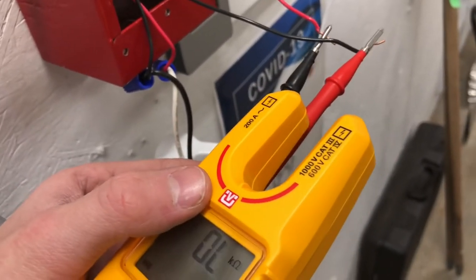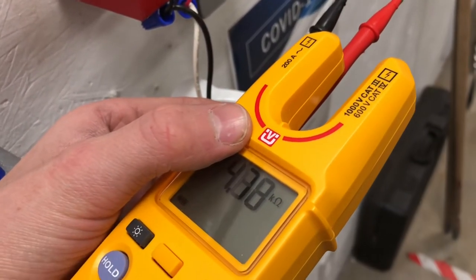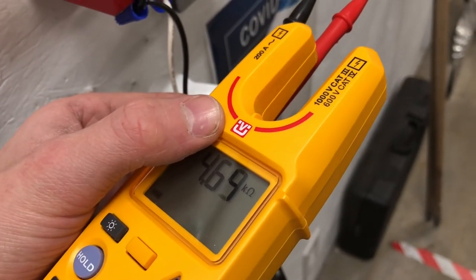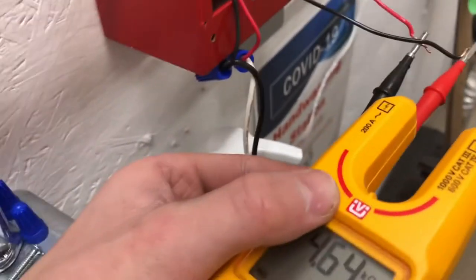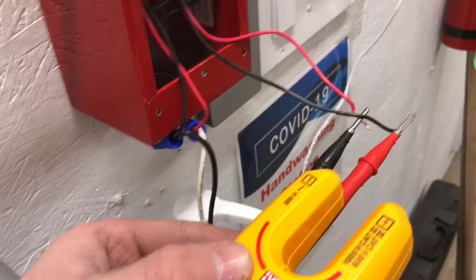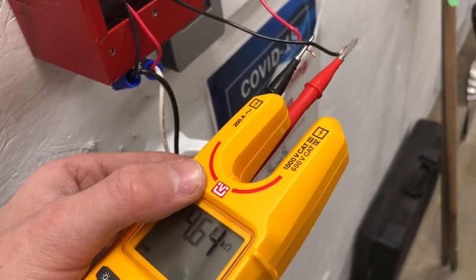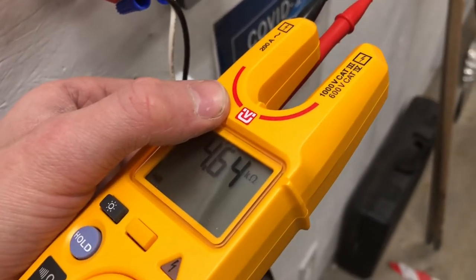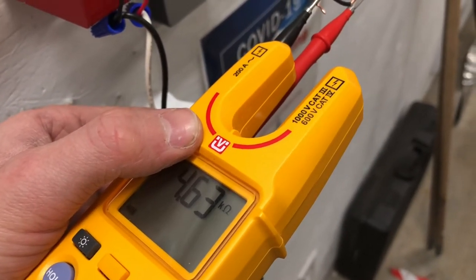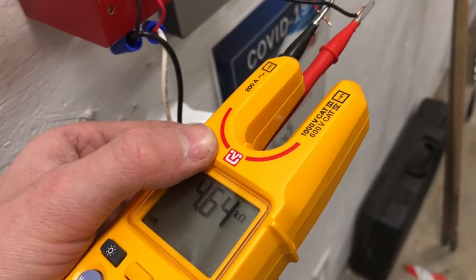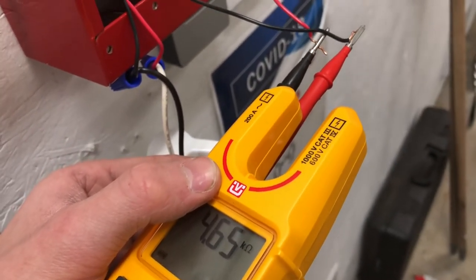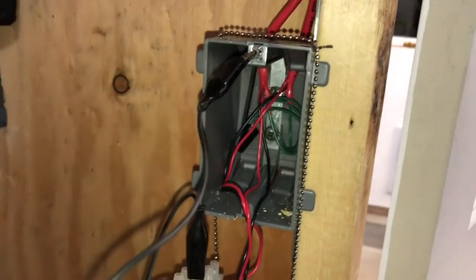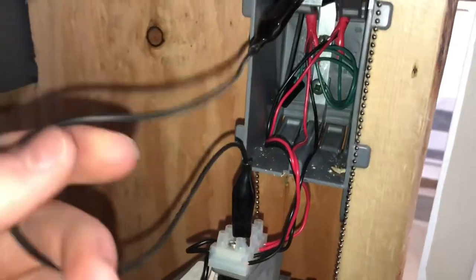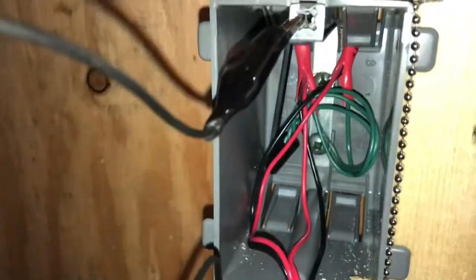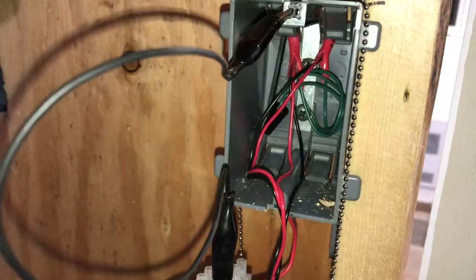But then if you get your meter between the two and you get your 4.7K ohms, then you know you've gone beyond the ground fault, since you've disconnected the ground fault from the line side of it and now you're on the load side, towards your end of line. And if you don't have any continuity from either one to ground, then you know you've gone past your device and you could go back one, assuming you went to every other device. Now you've gone back one device, and it might be apparent that your ground fault is at this device, that you can visually see that something is making contact to ground.